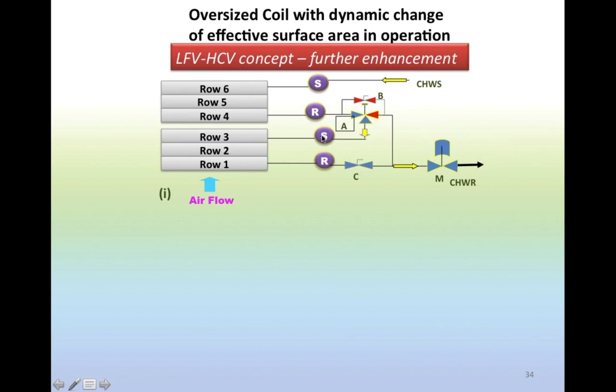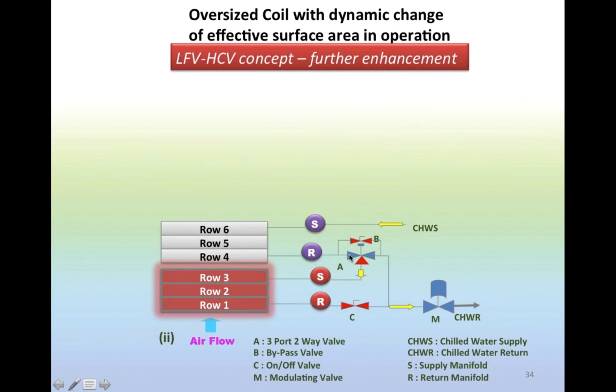The water could be circuited this way, and in this particular configuration, I closed this valve. So basically, only 3 rows are going to be used. What's happening here is these 3 rows still exist there. They are just a dead component of chilled water tubes in the circuit. It's not contributing to any performance, but that's okay. I'm now effectively working with a smaller cooling coil.